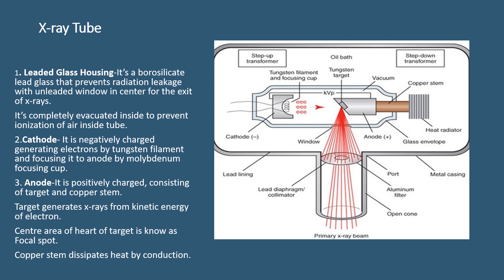The cathode has a negative charge and has two parts: the tungsten filament and the focusing cup, which is made up of molybdenum. The function of the cathode is to generate electrons by the tungsten filament and focus them toward the anode by the focusing cup.